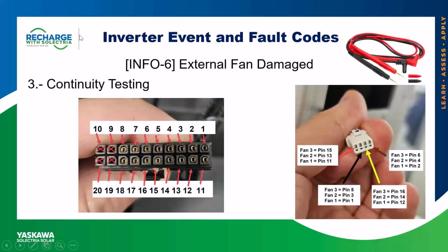And to test that, we recommend to check continuity on the fan harness. It is recommended for this troubleshooting procedure that the technician has fine leads, as you can see in the slide on the top right corner, to be able to test the connection points. Since with regular leads, it is not going to be possible to perform this troubleshooting procedure. I'm going to explain what the pictures are referring to. If you go ahead and you remove the pin from the actual fan, the wiring harness is going to show on the right-hand side, looking at the picture.